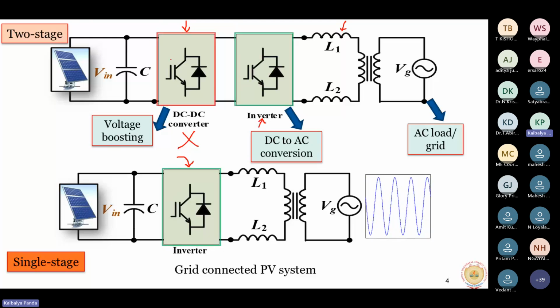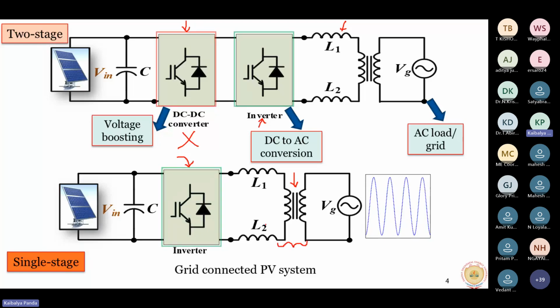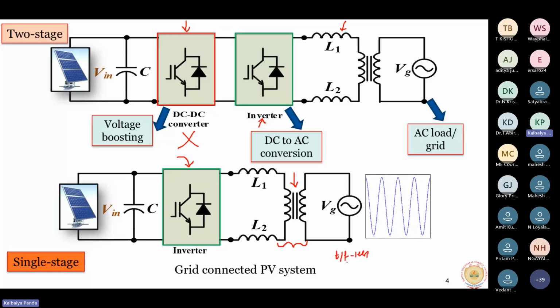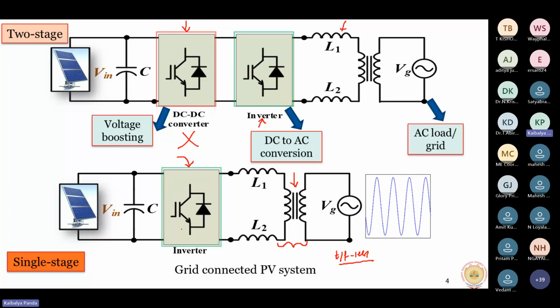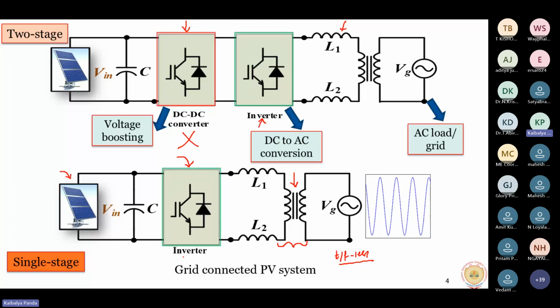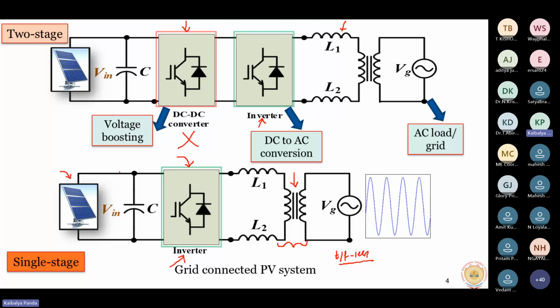Now there's a critical aspect to focus on: here I have used a transformer. If you want to also remove this transformer from the grid side, to design a transformer-less system for grid-connected applications using photovoltaic or other renewable energy sources, then the inverter should be capable of boosting the voltage. Otherwise you cannot efficiently utilize the solar photovoltaic power for the grid.